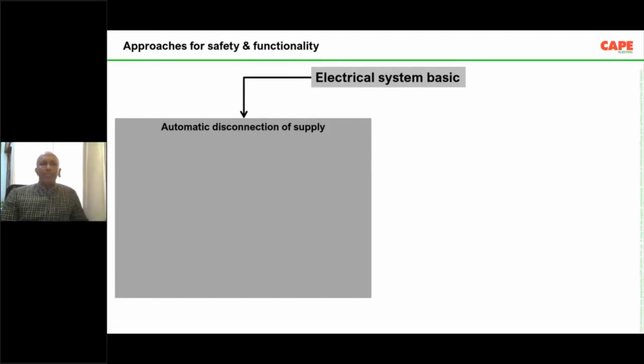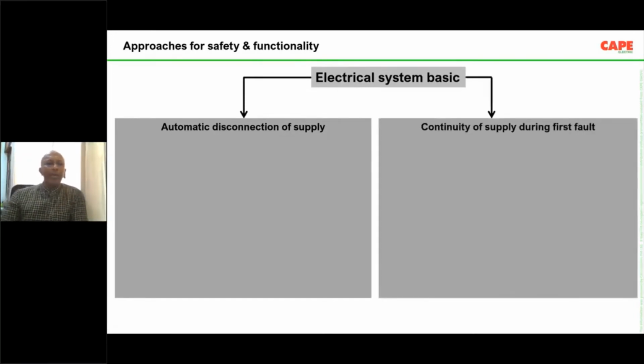There are two approaches in the design. The first approach says, in case of any problem, automatic disconnection of the supply is the solution. That means in case of any insulation breakdown, your MCB should trip. In the second case, continuity of supply during the first fault. What does it mean? You have an insulation failure in your building, but the supply shall not trip. So the method to handle the first case and the second case, the concepts are entirely different.